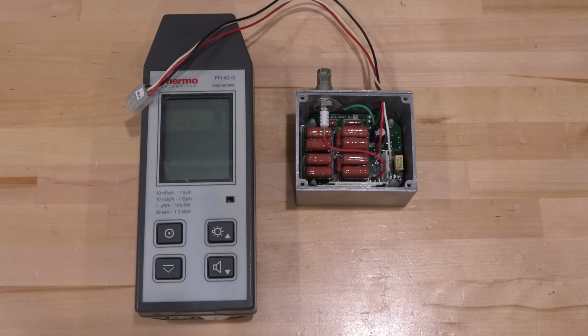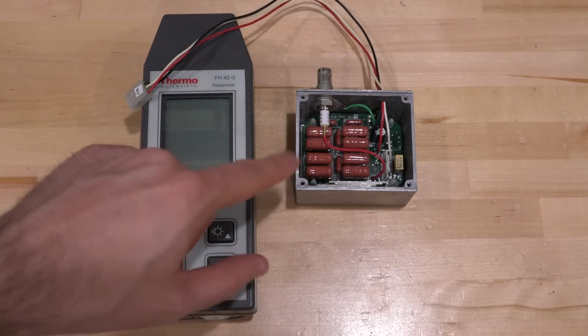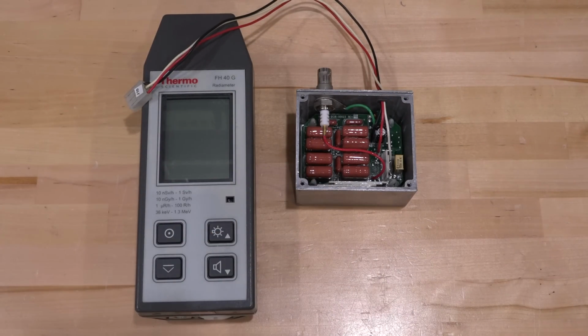Well, to measure the high voltage power supply required for the detector tube was pretty easy. That was this box right over here, which had a cover on it that said do not adjust. And that's because this high voltage power supply has to be very accurately set in order to be able to make the correct measurement of the spectrum. Otherwise, the whole thing will be shifted. So as a result of that, they don't want you to mess with it, but it's a standalone unit.